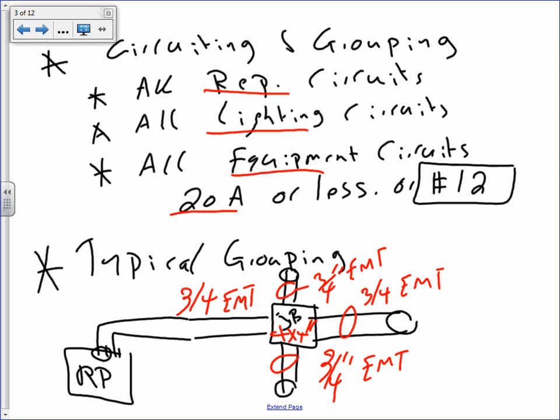Okay, in a 4 box, and from this ceiling I can take another 3/4 of an inch to go to another J box, another 3/4 of an inch to go down to a receptacle, or sometimes we go down with a 1/2 inch if we're going down to a receptacle, from the top down. We pick it up with 1/2 inch. But that's typically when you deal with conduits: you take a 3/4 of an inch to a J box in the ceiling, and from there you spread. You go to another J box, a third J box, and you start picking up these receptacles. Go here, down, drop, pick up receptacle, drop, pick up receptacle. That's one way of doing it.